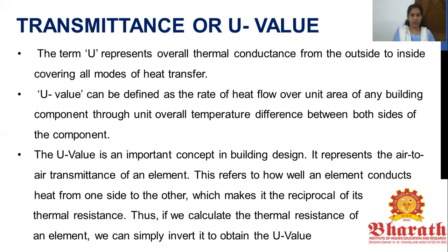This refers to how well an element conducts heat from one side to the other, which makes it the reciprocal of its thermal resistance. Thus, if we calculate the thermal resistance of an element, we can simply invert it to obtain the U value. Or we could take one piece of data and reverse it to find the other. So imagine I have the resistivity value, I can get the conductivity.